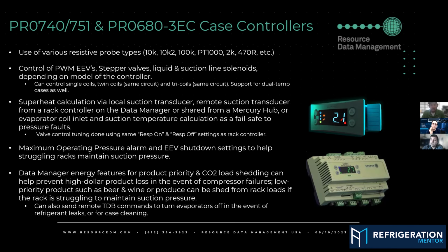One thing to look for with those, especially during startup, sometimes valve wires can get swapped around, or suction sensors can get swapped around on each coil. So then they'll kind of control off of each other. So you'll see a valve that's completely closed, but the superheat's really low. And another valve, the superheat's really high, but the valve's way open. You pull a graph and they're just crossed with each other. That's a very good indicator that you've got something cross-wired.